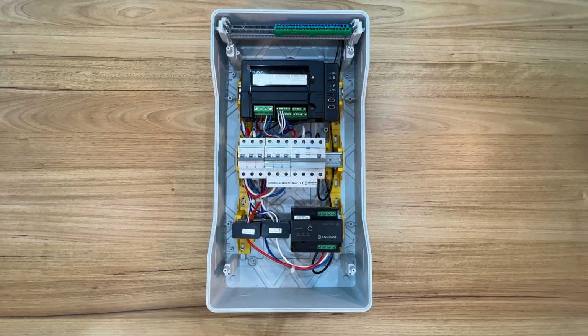Now it's very important that you have correct phase wiring for CTs. So it's worth marking or color coding each end of the CT flying lead so you can easily confirm that you have wired the correct phases across to the IQ gateway. It is always important to ensure that the phases are matched up correctly, along with the power supply phases connected to the IQ gateway. So for example, I have the red phase on terminal L1 of the IQ gateway, and I'm also measuring L1 for the production CT.